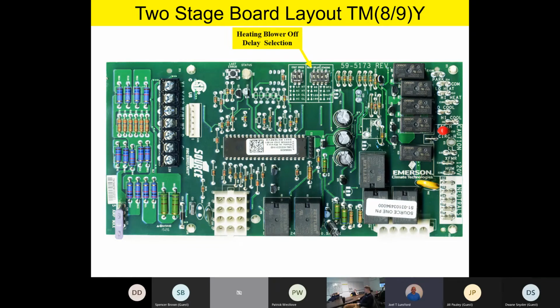Typically from the factory, we set them up at 120 seconds. But as you can see from the dip switch selection, you can go down to 60 seconds, which is still perfectly safe for the furnace as far as cooling the heat exchanger down. Or you can go up to 180 seconds to get all the heat off that heat exchanger, which makes it a little bit more efficient. So really, this is kind of a comfort setting.